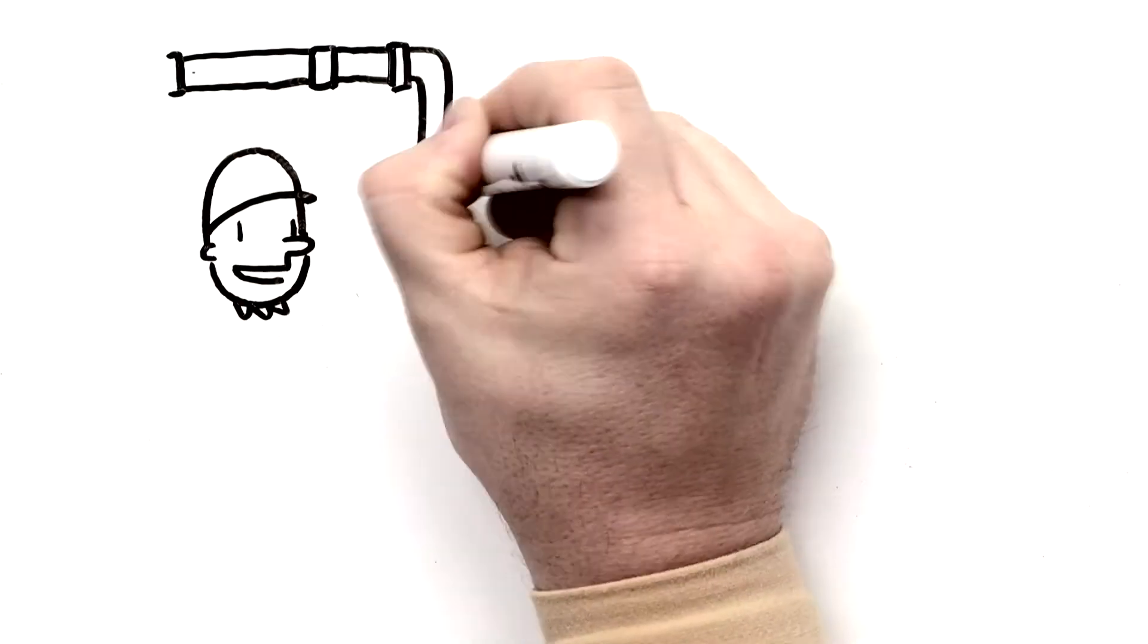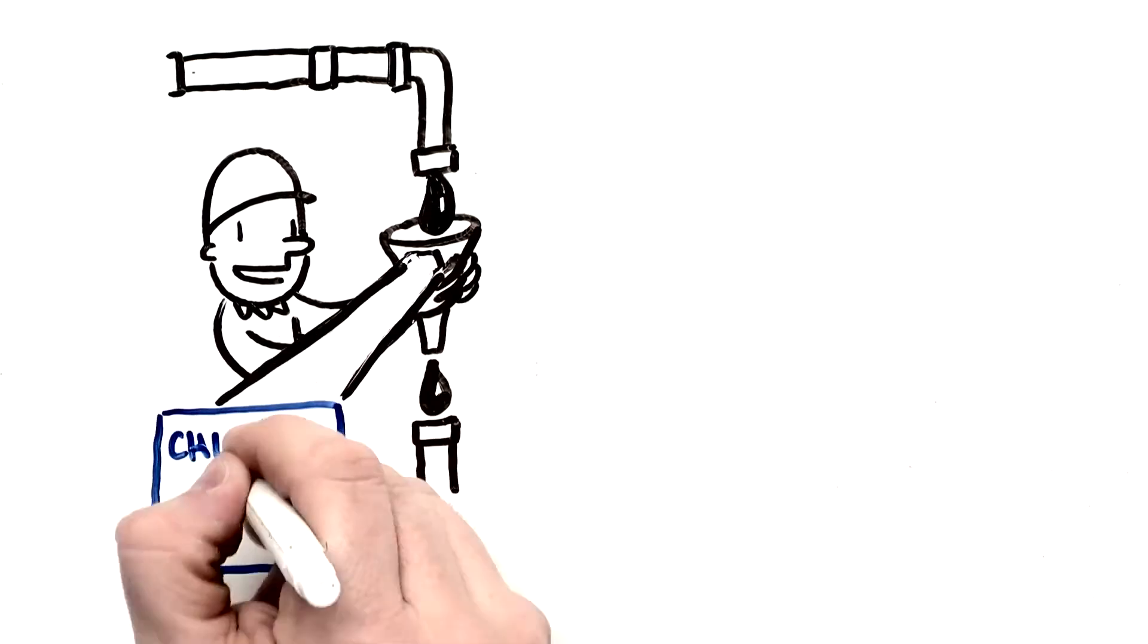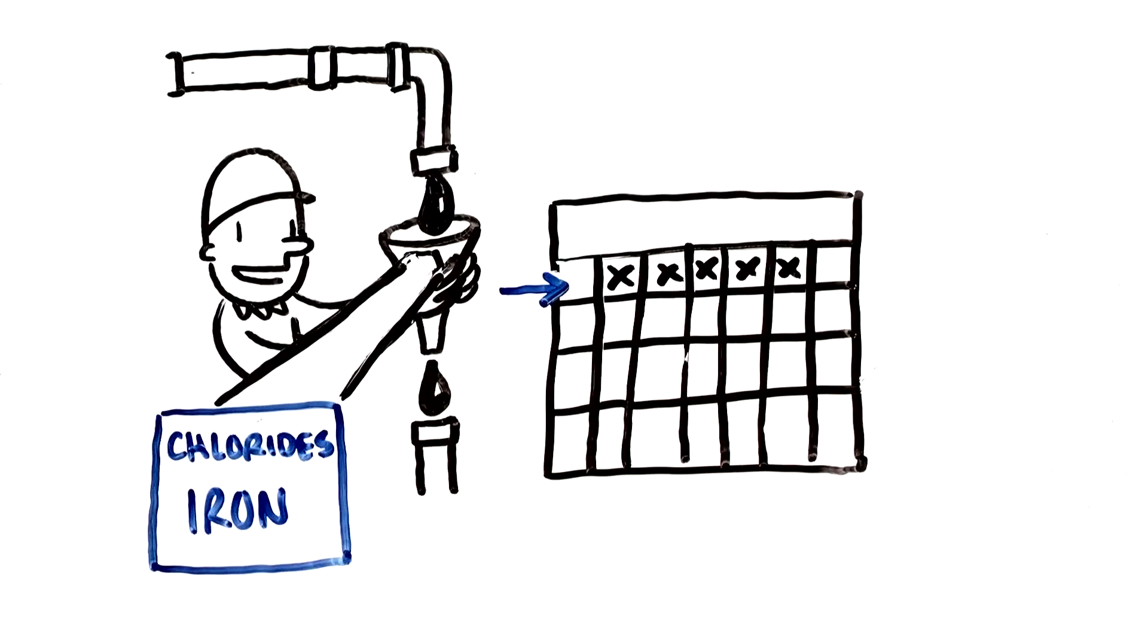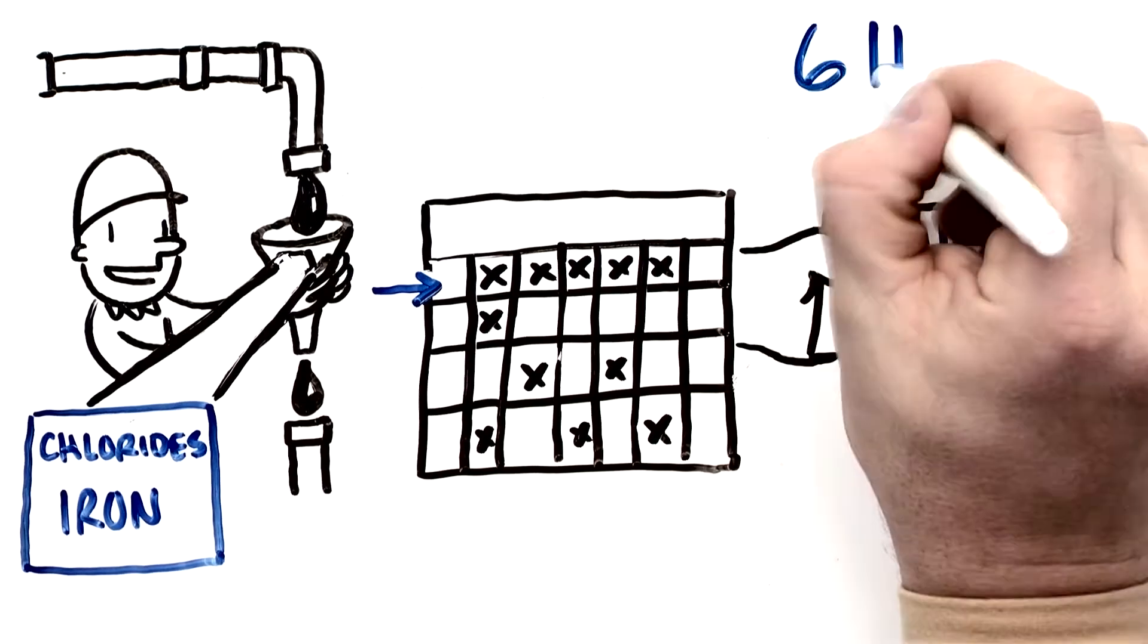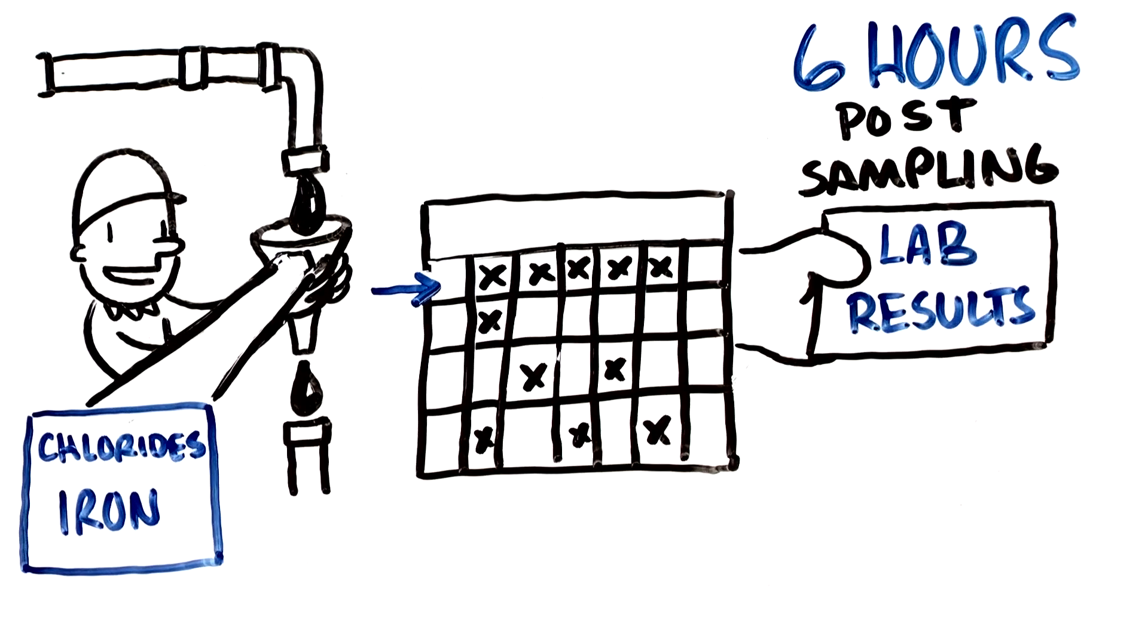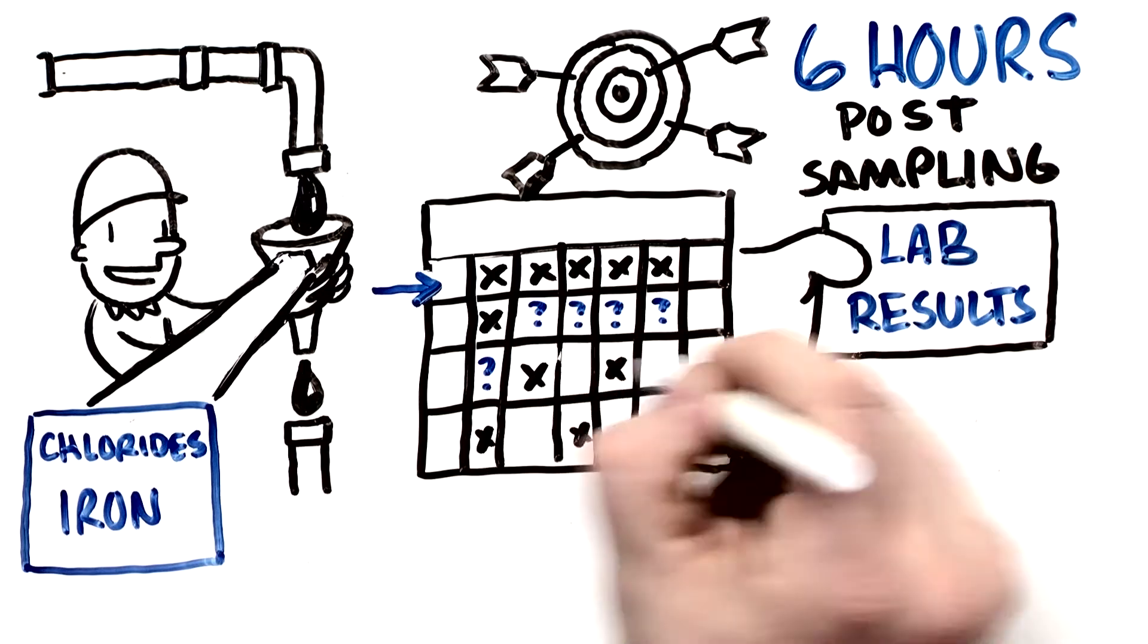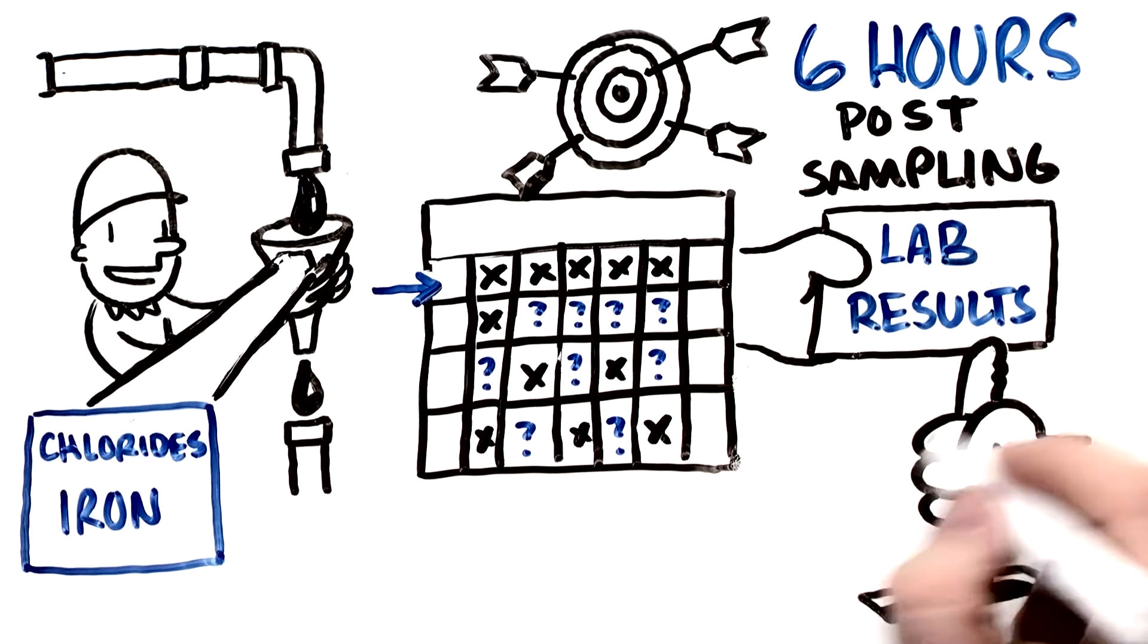The majority of refiners sample at best daily for chlorides and iron, but most sample only one to three times per week. Lab results are sometimes up to six hours post-sampling. This variability and infrequency of sample collection can have an impact on the control scheme.